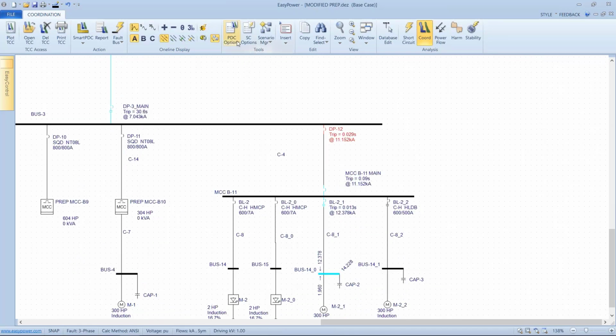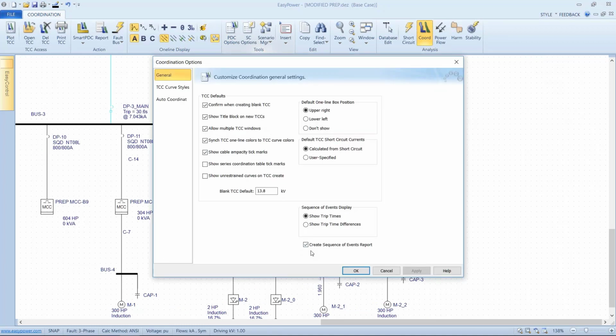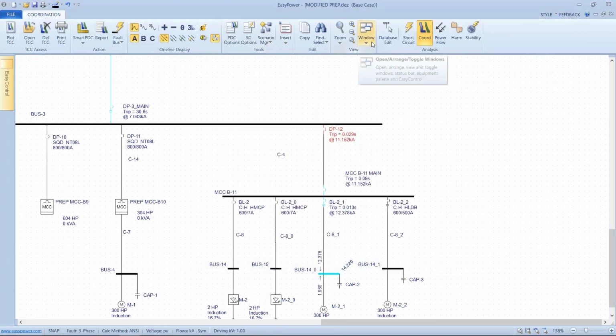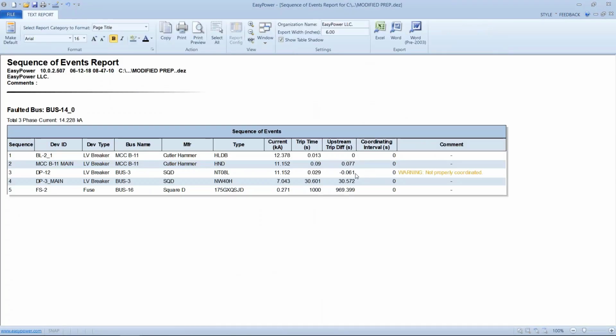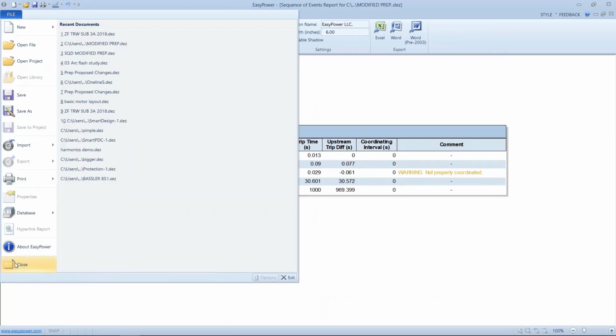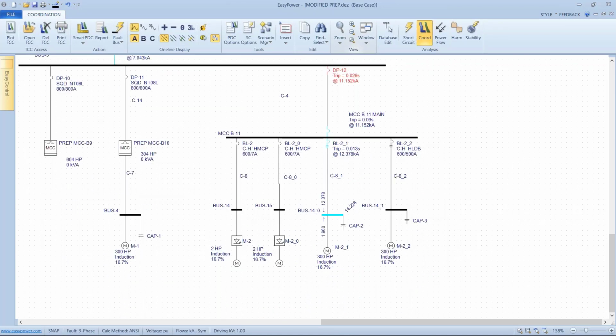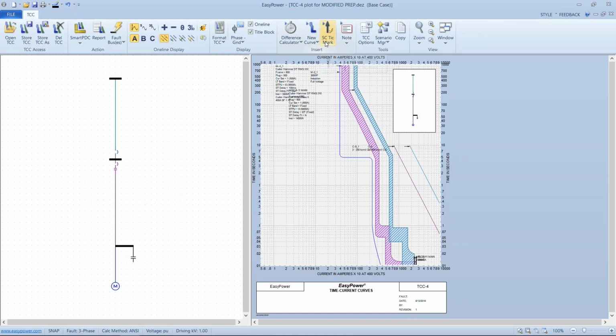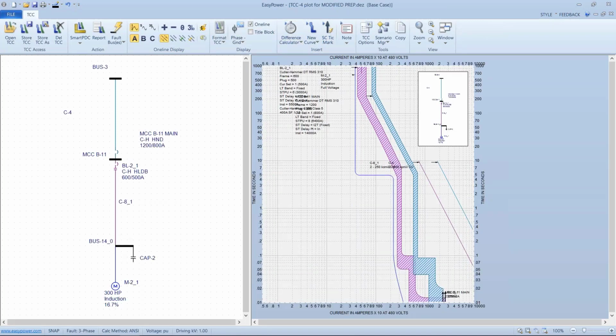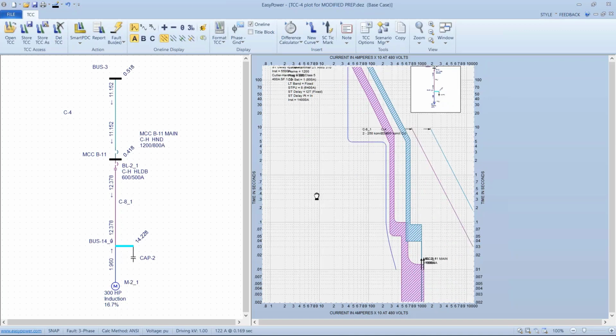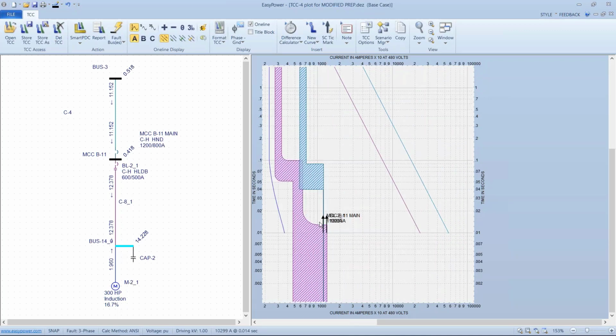Now, if I wanted to see a report for that, under my PDC options, I'd check Create Sequence of Events Report, and then under my list of windows, I would be able to display that. So the basics from that point on don't change. I want to pick out my load, the first couple of protected devices, plot the curves, look at as much as I can, the current if that bus faults, and then whether or not we have coordination for each of the trip devices above it.